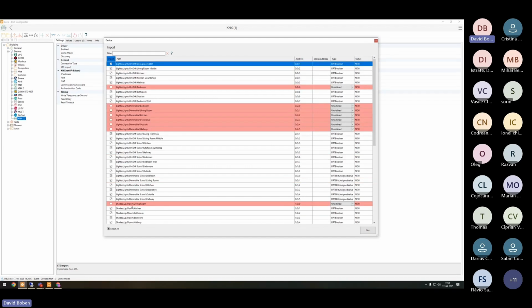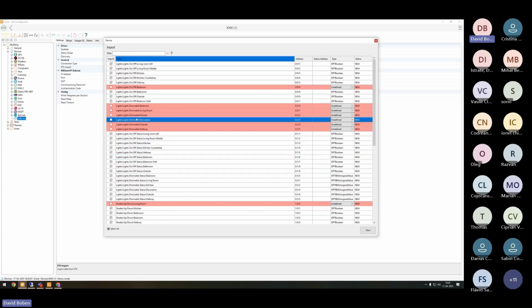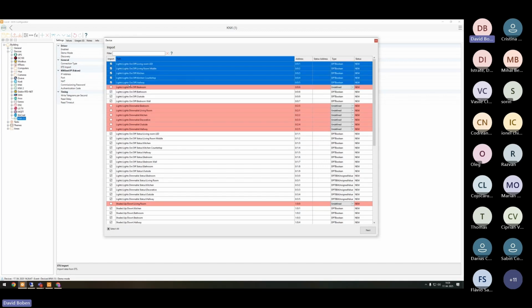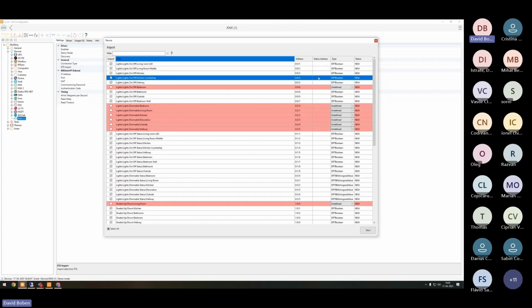As you can see, the majority of them are white, but some are colored red. If they're colored red, this means they were undefined in ETS - if a group address is undefined in ETS, it will also be undefined in BOS. If we still want to use this group address, we just need to set the correct type. Here you can see we have a path, which contains the name - we can see we have on and off, which is usually a Boolean value. So for lights on and off, right click and select Boolean value. Extremely fast, extremely easy to do.